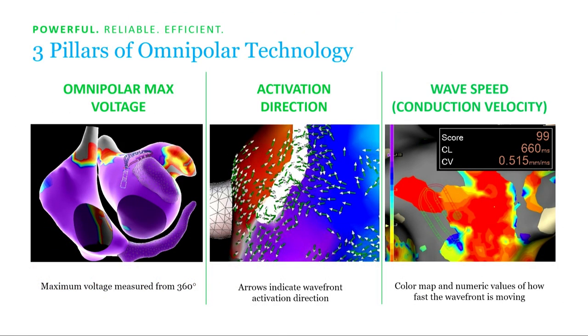Omnipolar technology enables three things: omnipolar max voltage—determining the maximum bipolar voltage in any 360-degree angle; activation direction from the HD grid poles, importantly independent of a far-field reference; and the ability to look at conduction velocity wave speed within the chambers, something conventionally only possible in basic science labs with optical mapping.